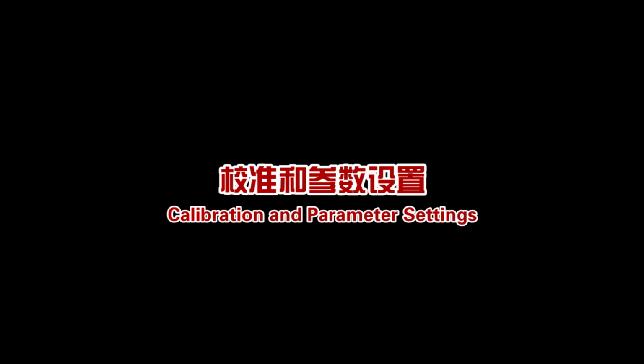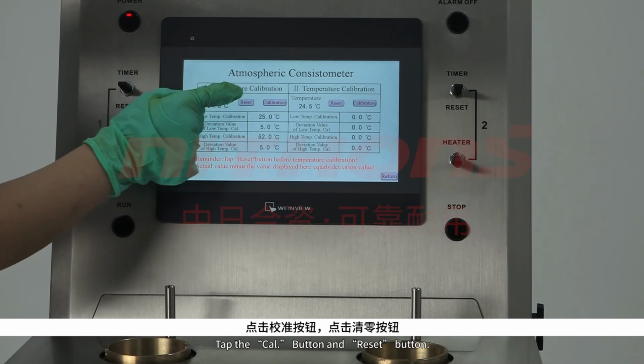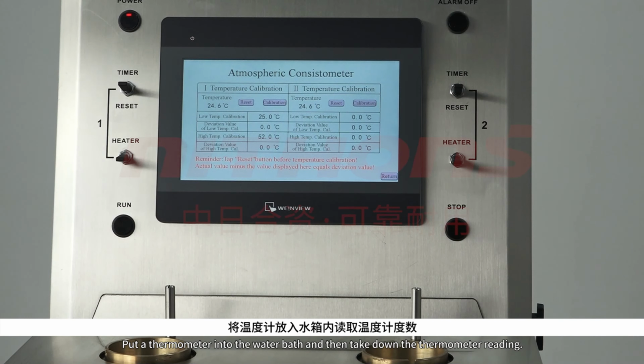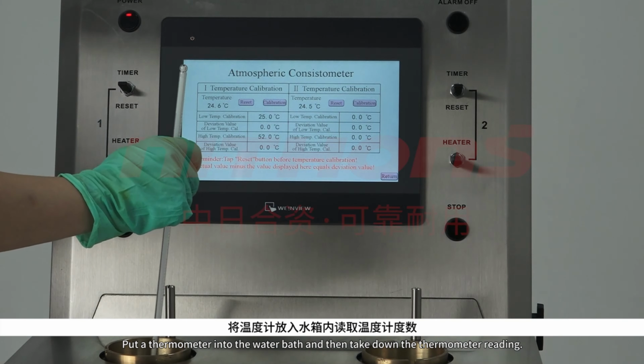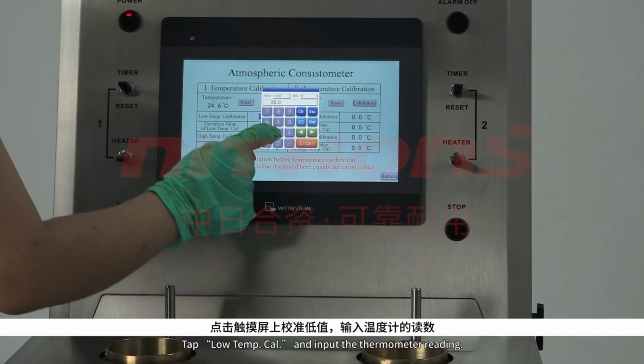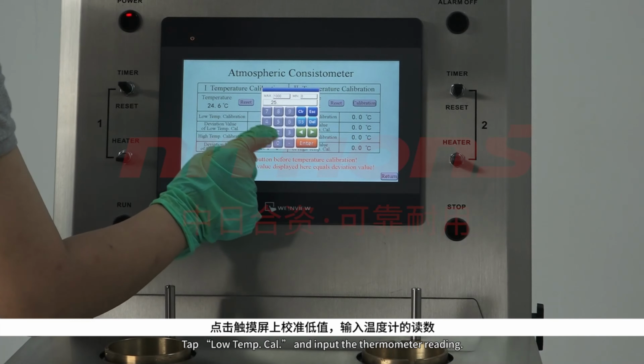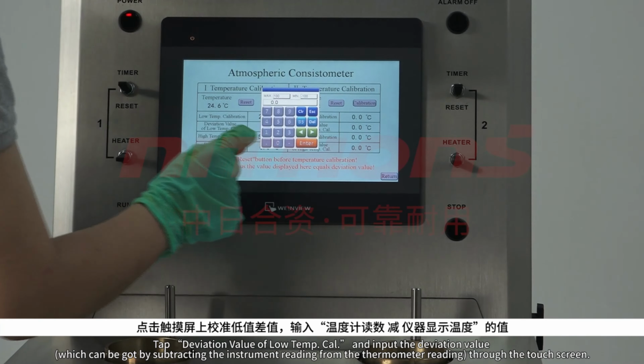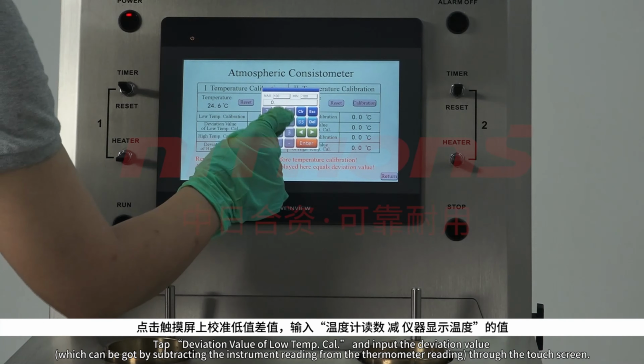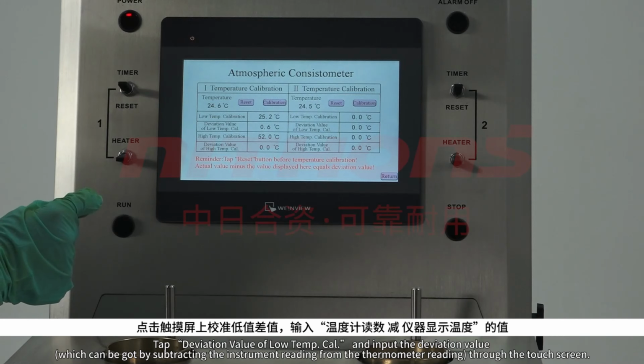Calibration and parameter settings. Temperature calibration. Tap the cal button and reset button. Put a thermometer into the water bath and then take down the thermometer reading. Tap low temp.cal and input the thermometer reading. Tap deviation value of low temp.cal and input the deviation value through the touch screen.